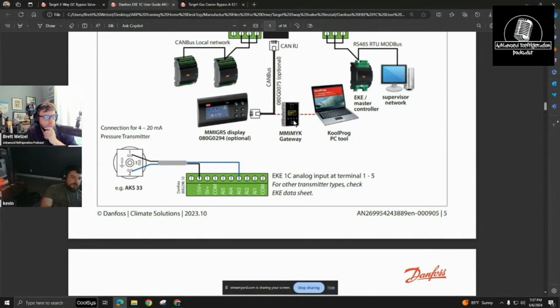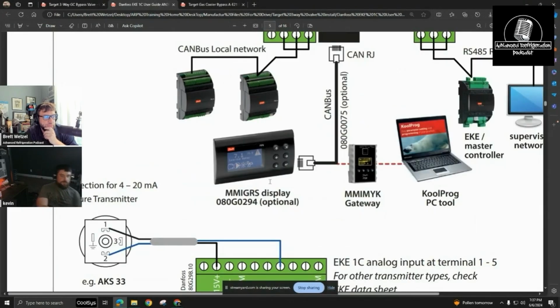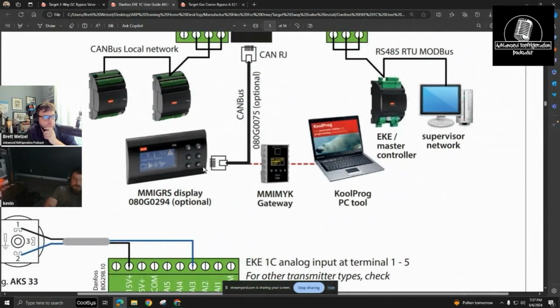And then that screen, that's what you need to address it and set it up. Super simple. Give it a 0 to 10 volt signal. You can make it inverse or direct acting, and it just drives the valves.